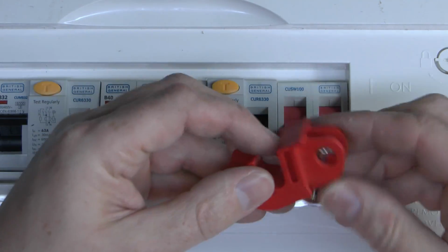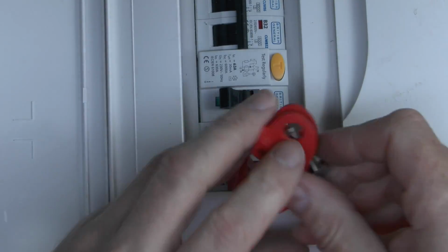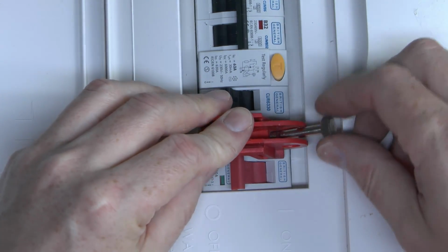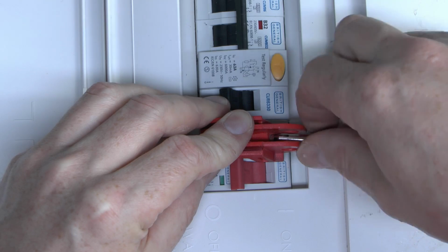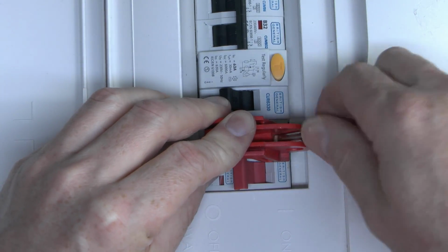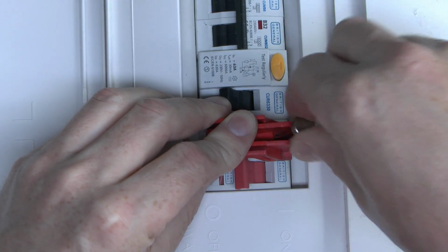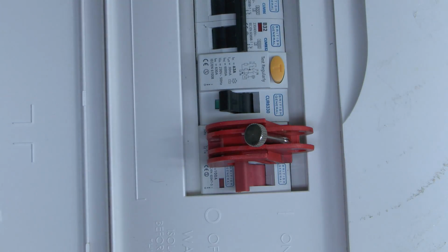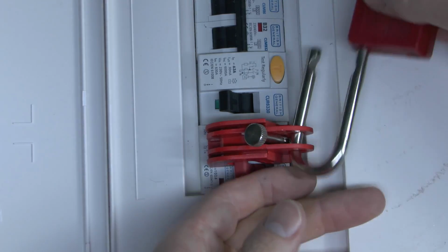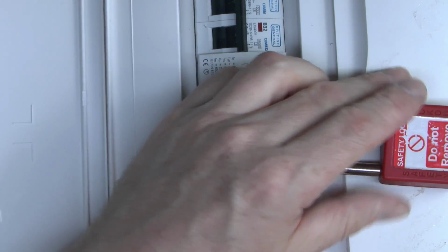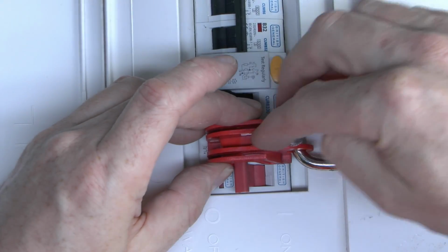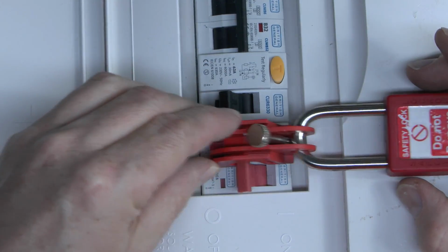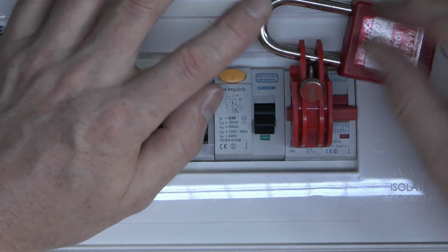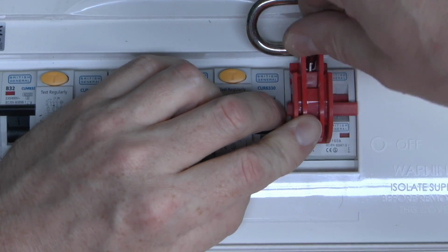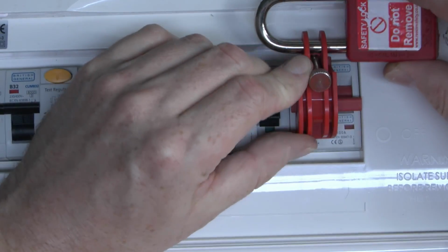This may fit onto this main switch here. This arrangement really is the most awful ever, but essentially you place that on there, tighten up the fixing here, making sure it grips onto the switch itself, fold that forwards, and then your padlock goes through. Then you can't move that into position to undo it, and it prevents the main switch from being operated. That's what it looks like from the front - you can't move this up far enough to turn it, and again it prevents the switch from being moved to the on position.